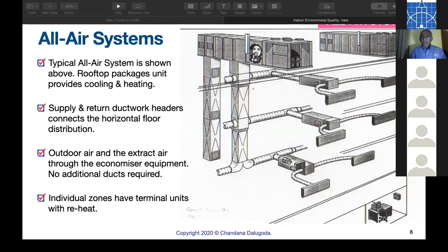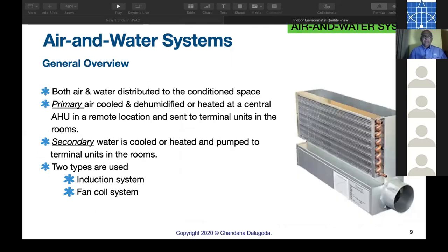But basically it is rooftop, a lot of advantages. You don't need a fresh air duct. You don't need to worry. You don't need an extract duct. Everything is handled by itself. There's an economizer. You can use it if it is in a four seasonal country. So in one way it is having a huge advantage, all air systems. Then comes the air and water system.